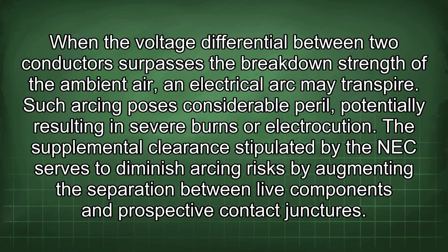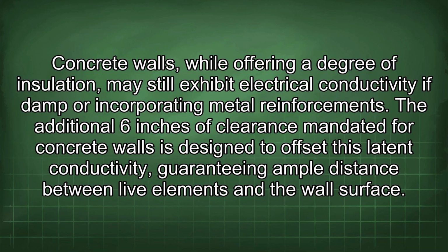The supplemental clearance stipulated by the NEC serves to diminish arcing risks by augmenting the separation between live components and prospective contact junctures. Concrete walls, while offering a degree of insulation, may still exhibit electrical conductivity if damp or incorporating metal reinforcements. The additional 6 inches of clearance mandated for concrete walls is designed to offset this latent conductivity, guaranteeing ample distance between live elements and the wall surface.